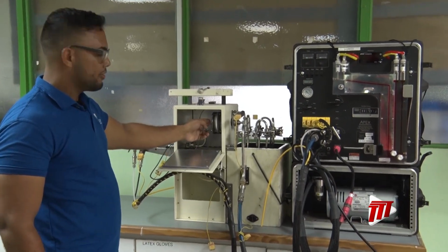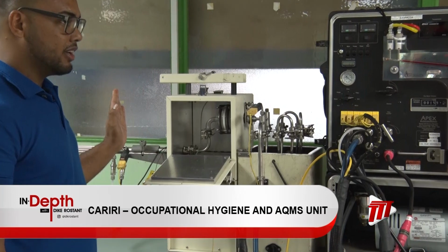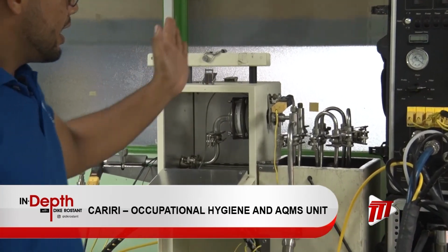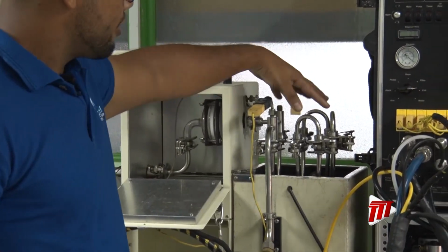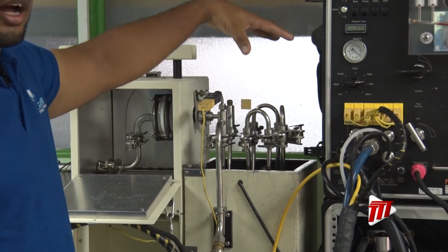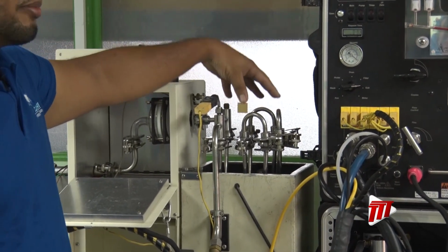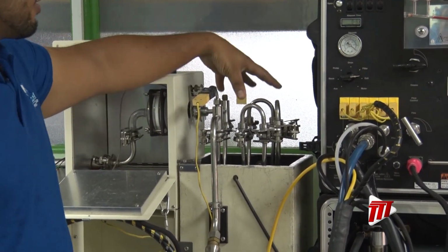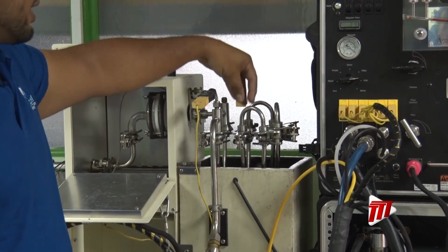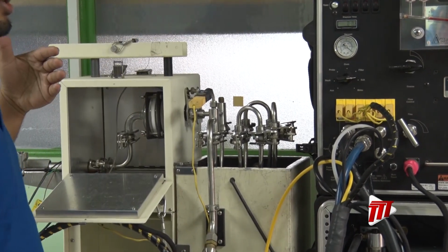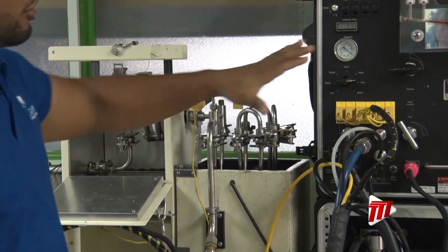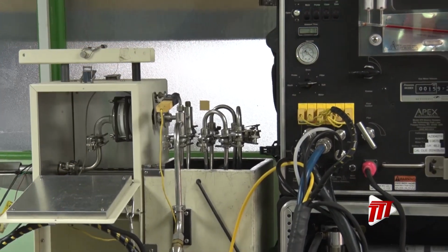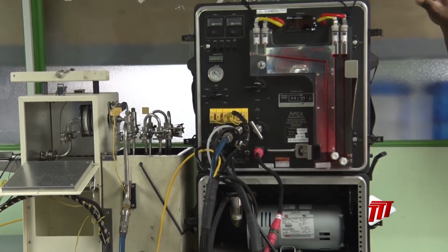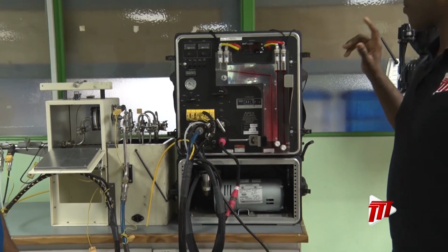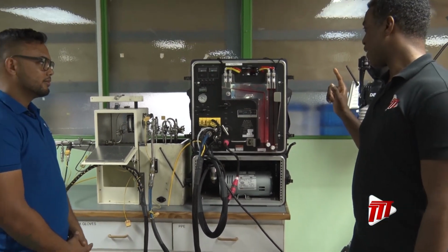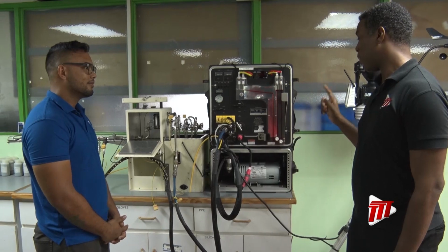It impacts on this filter paper here, so it removes the particulate, or traps the particulate matter. The dry gas now goes into these impingers, and these can be replaced with different reagents, depending on whether you want to monitor for dioxins and furans or heavy metals. We capture these reagents and carry them back to the lab to analyze, and everything is controlled through this right here. You explaining all of this to me, Matthew, and all I studied is that somebody had to be toting this up the stack.